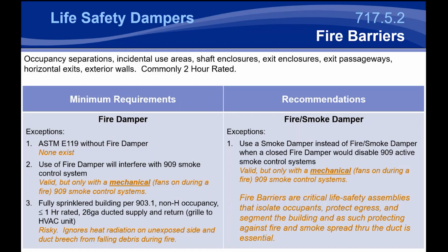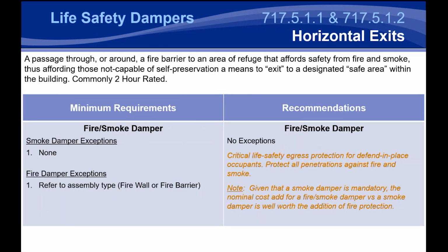That's why we think it's a little bit risky when you're dealing with fully ducted applications, especially if they're 2 hour rated. Now, if it's 1 hour rated, there are some applications where it is still risky, but it's less risky than, say, this application, typically when you're dealing with corridors where there's penetrations that don't actually service that corridor. But there is always a bit of a risk for that duct to be dislodged if it doesn't have a damper protecting that barrier, regardless of the hourly rating of that barrier.